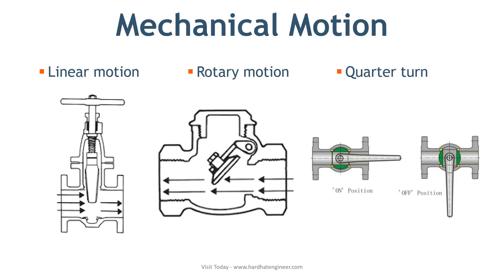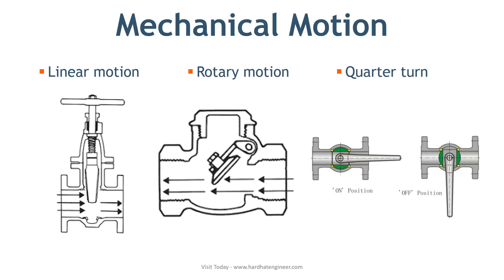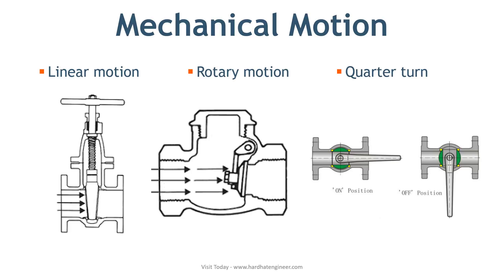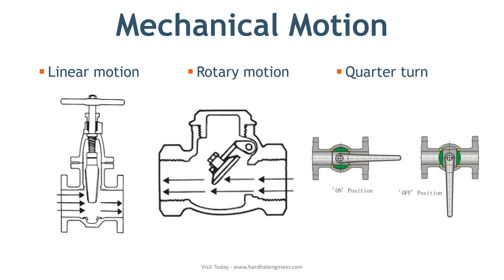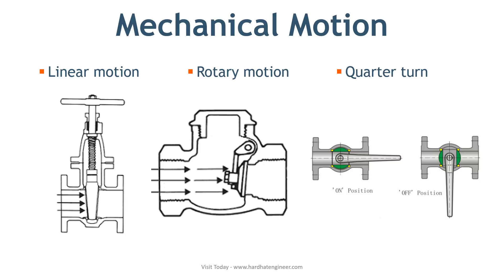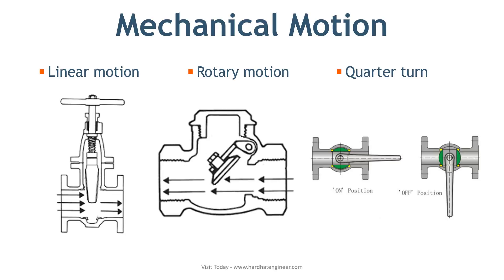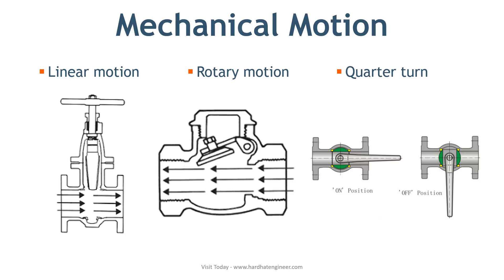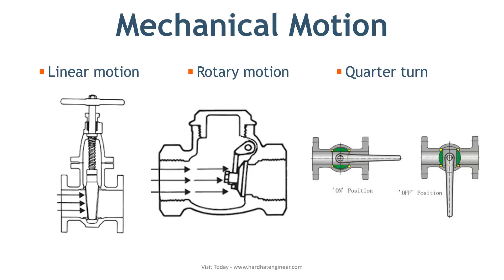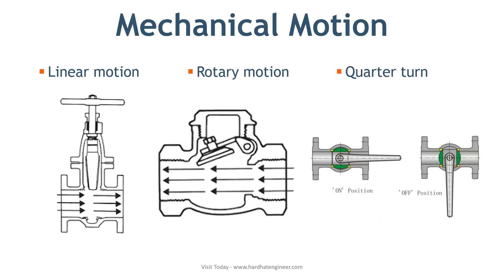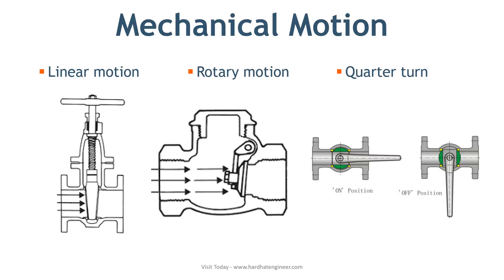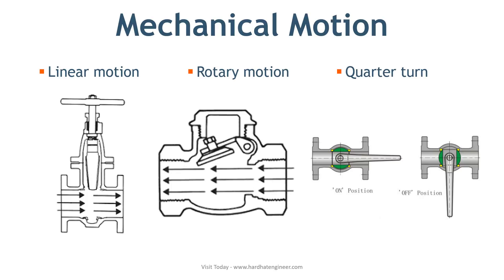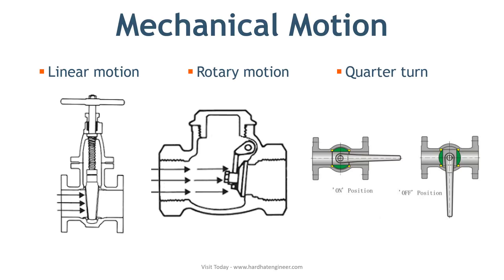In rotary motion valves, a closure member travels along an angular or circular path, as in butterfly, ball, plug, and swing check valves. Some rotary motion valves require approximately a quarter turn — that is, 0 through 90 degrees of motion — to go from fully closed to fully open, or otherwise.